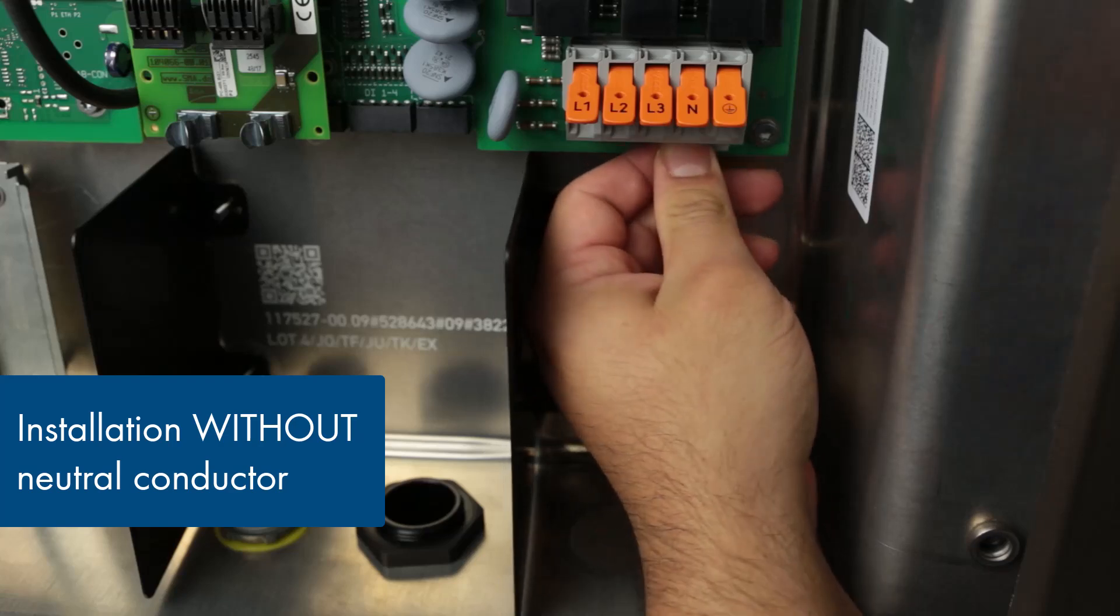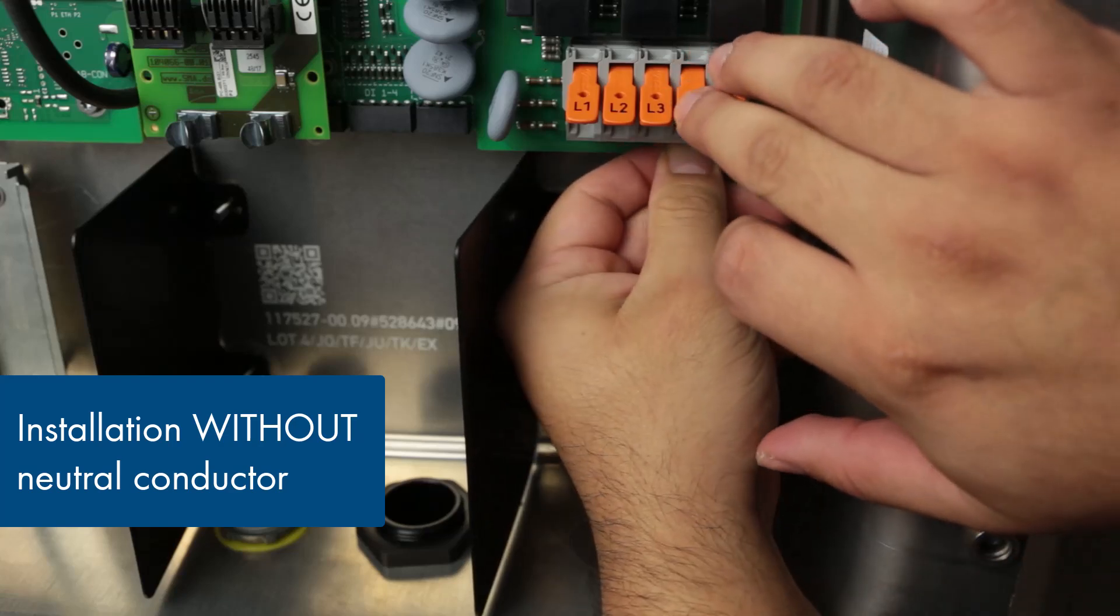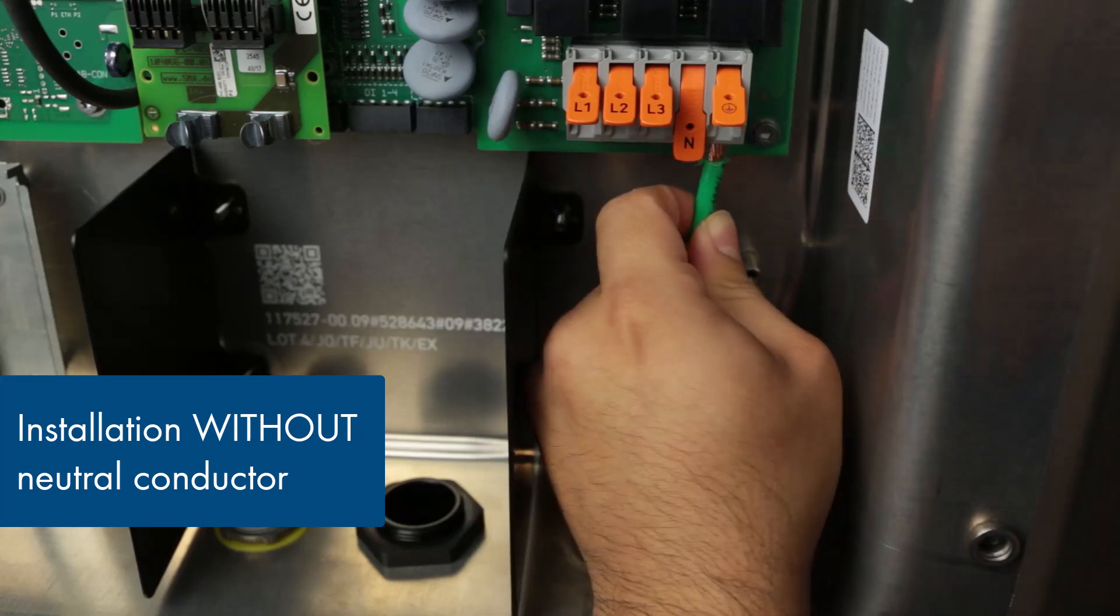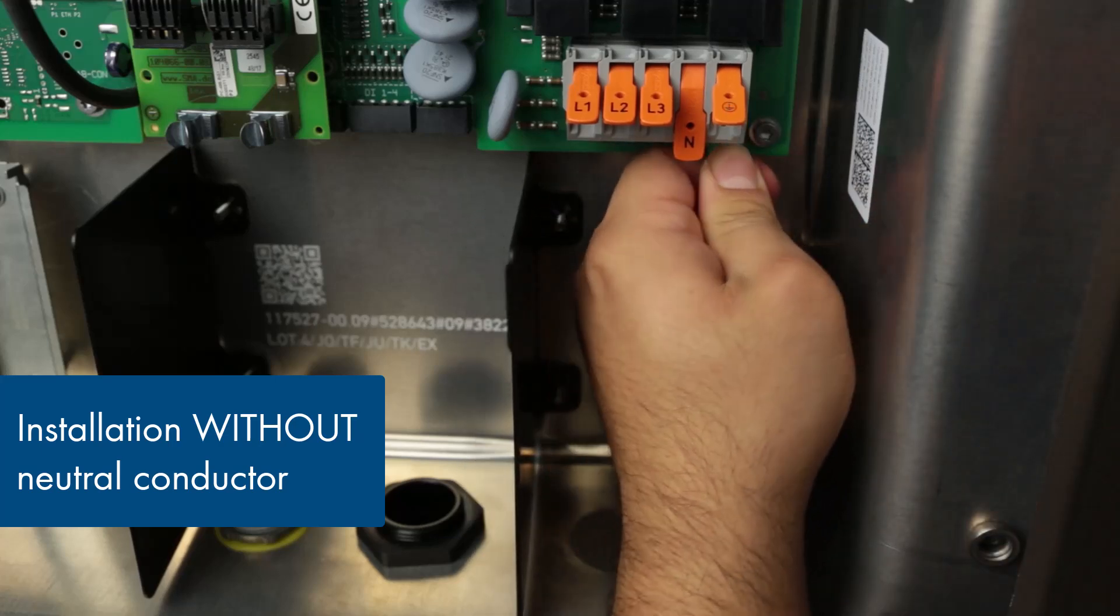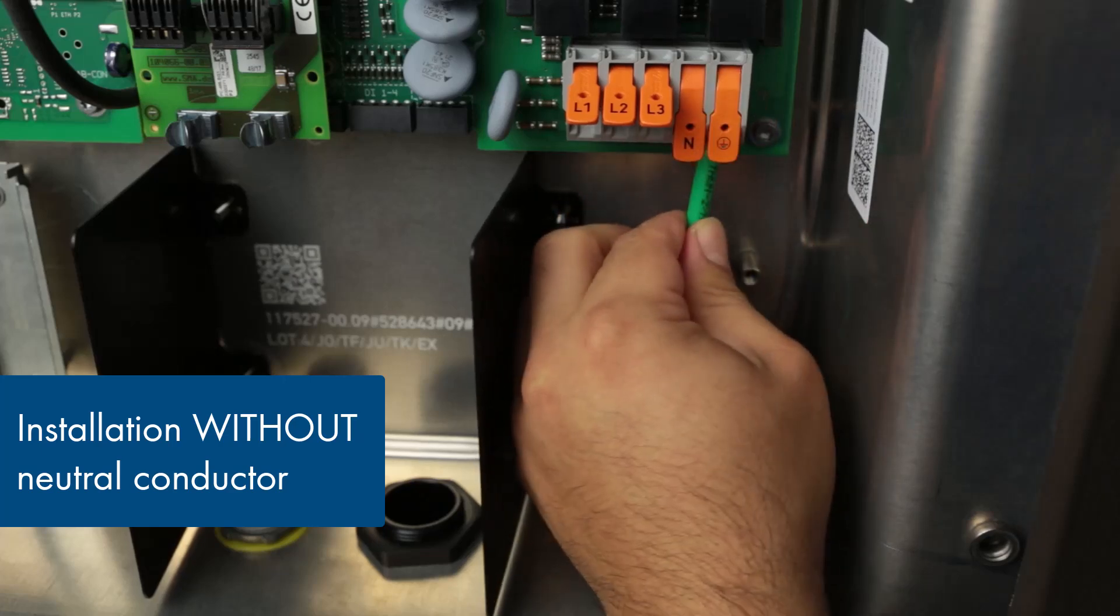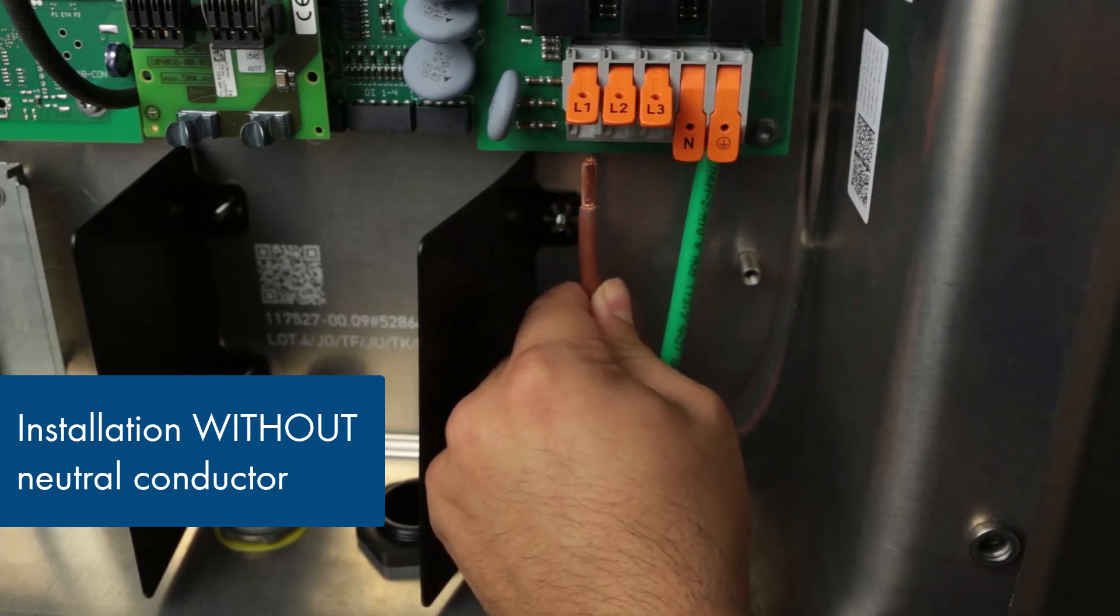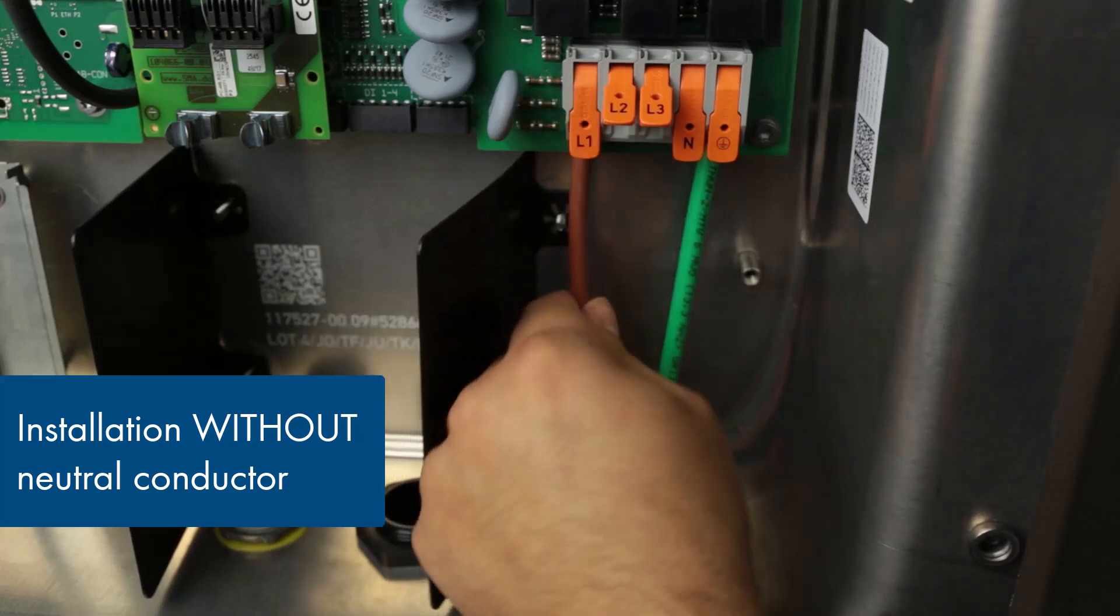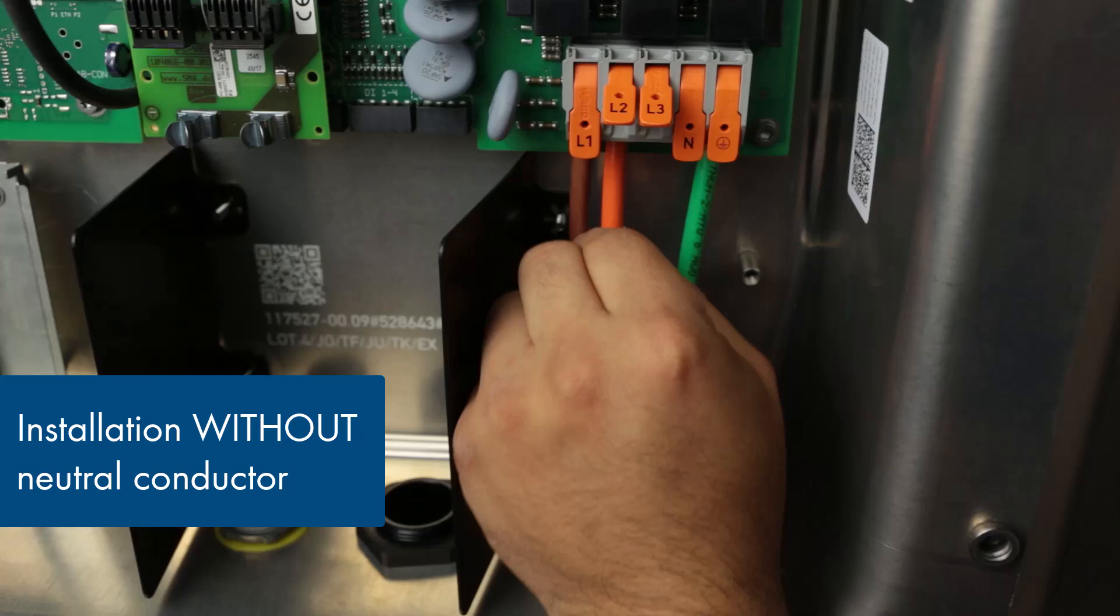Lift both the neutral and ground levers, insert the jumper, and close the neutral lever. Insert the ground conductor into the terminal marked with the ground symbol and securely close the lever. Proceed to insert the L1, L2 and L3 conductors into the respective terminals, ensuring a secure seating for each.